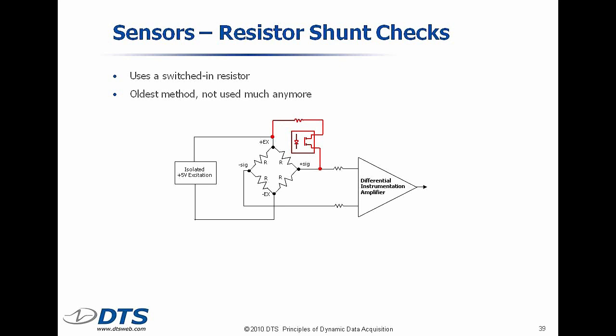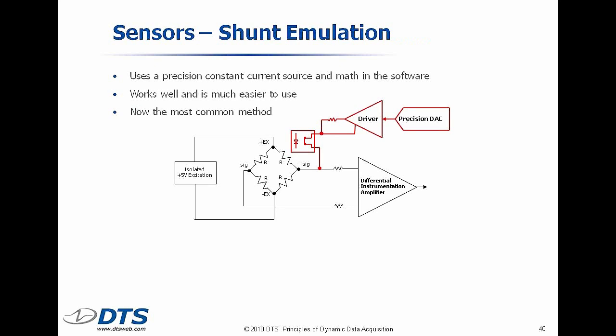Today, we use a technique that's called shunt emulation, and it basically does the same thing that old shunt tests used to do, but what it does is it takes the sensitivity of the transducer, it takes your desired full-scale measurement, the excitation voltage, and it actually calculates an exact shunting voltage to apply to the transducer to deflect it something like 100% of full scale. And so this technique is sort of under the hood, but it's now the most common method for simply doing a cross-check on the transducer and the wiring.